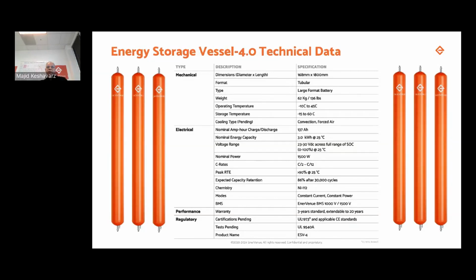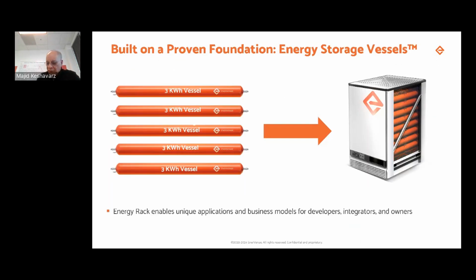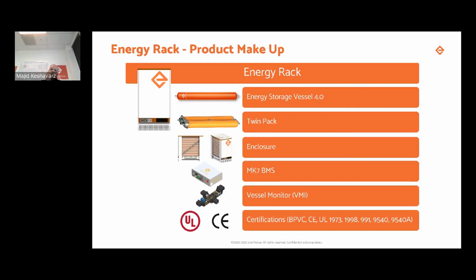This is the spec sheet of the new pressure vessel. It's a 3 kilowatt hour, 137 amp hour, 1500 watt nominal power. It's C/2 to C/12. That's typically the case in our BMS. We have two types, 1000 volts and 1500 volts, both certified. So the new racks for sale are based on the new 3 kilowatt hour design. We put 50 of them in a rack, and we're getting really good feedback from the customers. These racks come with a BMS as well as VMI, and also certifications.